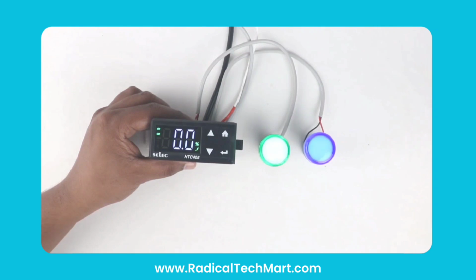The next parameter is humidity display bias. If your sensor location causes a difference in humidity readings, you can adjust the display bias here, up to plus or minus 19.9. Following that is the restart time delay. You can set a delay up to 19.9 minutes. This means after the relay turns off, it will not turn on again for the set delay time, even if conditions are met. Finally, there is a humidity reset option.